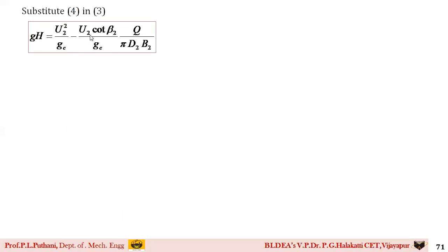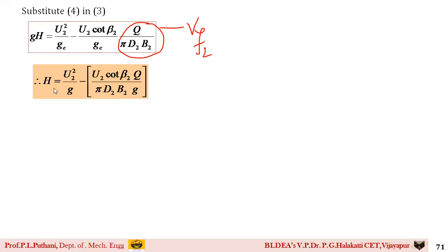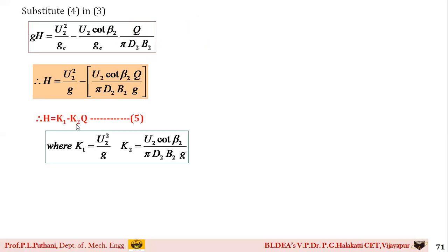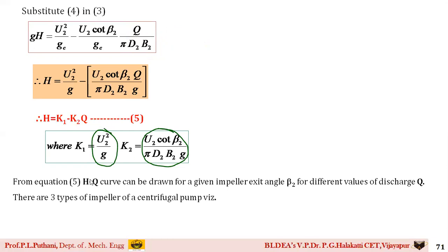After substitution, gH = U2² / gc − (U2 · cot β₂ · Q) / (π·D2·B2·gc). Writing in terms of g: H = U2² / g − (U2 · cot β₂ · Q) / (π·D2·B2·g). This can be written in the form H = K1 − K2·Q, a linear H-Q relationship. Using this, we draw the head-discharge curve (H-Q curve) for the impeller at different blade angles β₂ with varying discharge values.